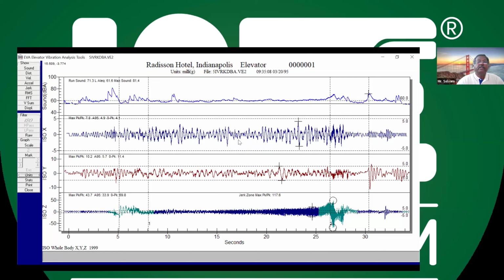It looks more simple. And if you see the peak to peak, it is now reduced. Earlier it was 53, now it is 7.8. Average value also reduced, to 10.2 and 5.7. But still, vertical vibration is very high, 43, and average value 33.